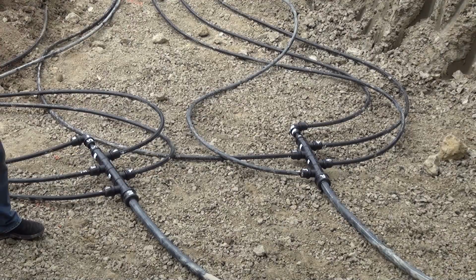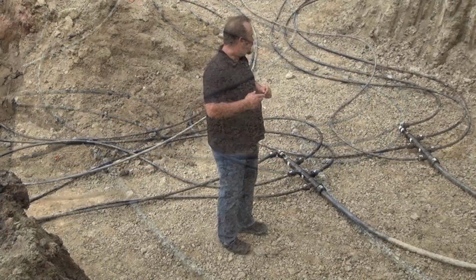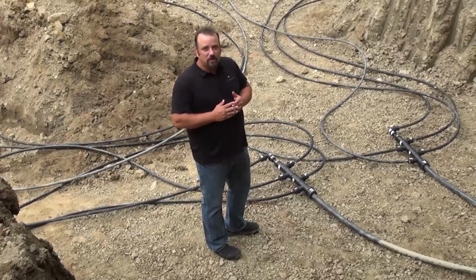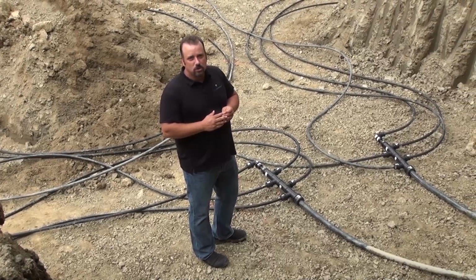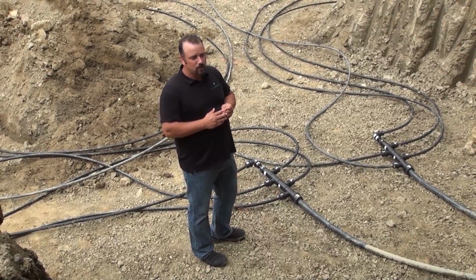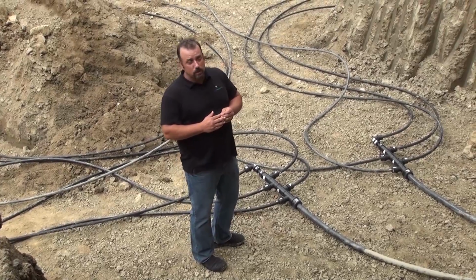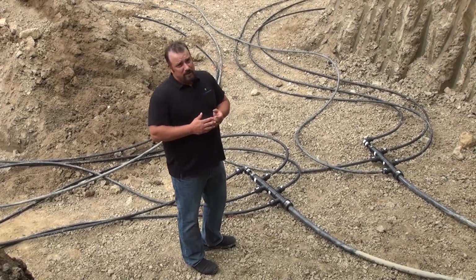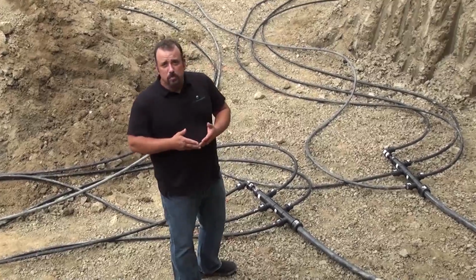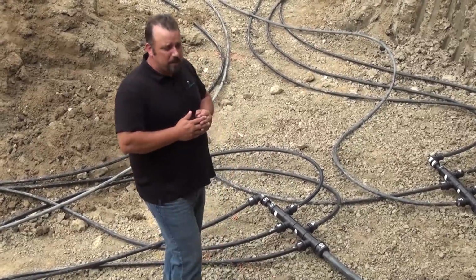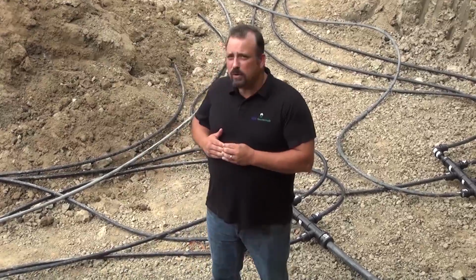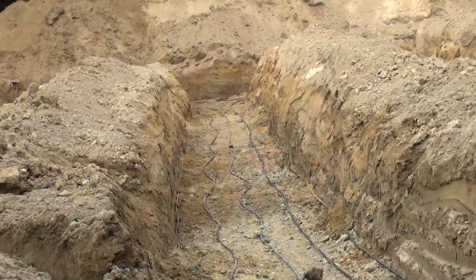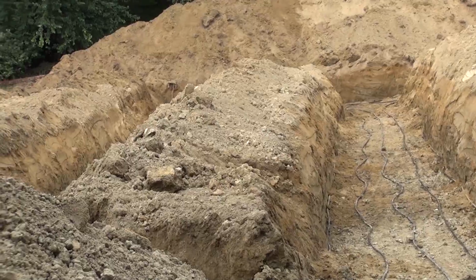These pipes are all hooked up in such a way that, in this particular application, everything is on the loop field side on the 3/4 inch pipe, which is all the small pipes you see coming into this 1.5 inch manifold header. All of these loops are exactly 600 feet in length. It is extremely critical to make sure that your loops are all 600 feet, that you don't have one loop that's 580, one that's 600, one that's 540. The reason for that is you won't get even circulation through the manifold system going into the house. We want to make sure that we are optimizing the amount of fluid that's going through all the loops and getting all the recovery from the ground that we possibly can here.